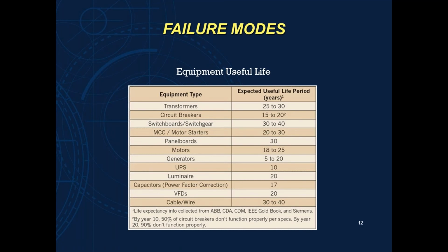This is kind of an alarming table here. If you look at it, many people don't really think about this too much. In the electrical world, we're used to hearing things like a 30 or 40 year design life of equipment. But if you look at things like generators, there's a wide range of expected useful life, 5 to 20 years. That's because, per all these references listed on the bottom, in their experience, in a lot of cases, generators may not be exercised like they're supposed to, and so when they're called to operate, they don't. Look at a UPS system, a battery-backed power system. You have a lot of components that just do not last very long, okay?